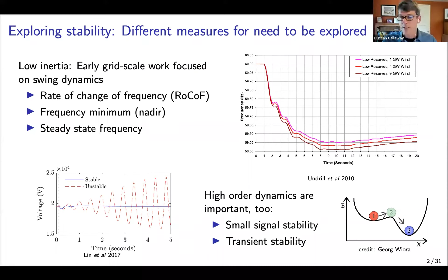Okay, so before I go further, I want to give you just a crash course on inverter control, because these terms, GFL and GFM, are going to come up a lot in the talk today. If we think about conventional inverters, an inverter is that power electronic device that takes your PV farm or your battery storage and converts it into an AC waveform to use on the grid. This is what the overwhelming majority of inverters on our grids do today. We call these grid following, in the sense that they will lock onto grid frequency using a phase locked loop and then track that frequency exactly. They'll have set points for real and reactive power and just adjust their waveforms in order to deliver that real and reactive power, but tracking the frequency of the grid precisely. So in this way, you can imagine it wouldn't work without a grid connection. You need to be able to sense that grid frequency to decide what to do with your inverter.